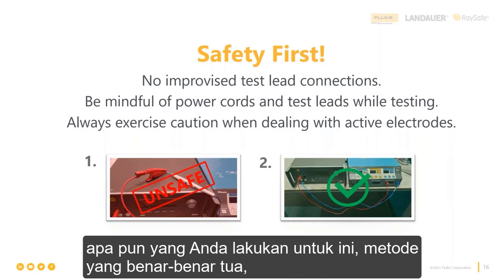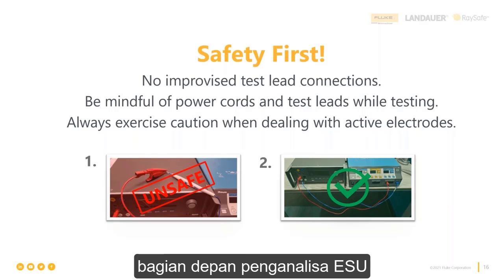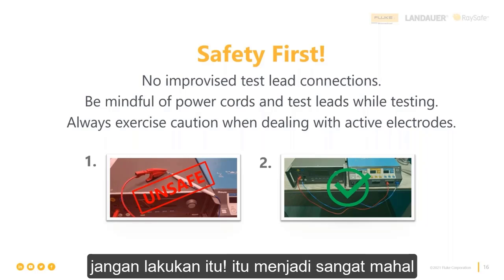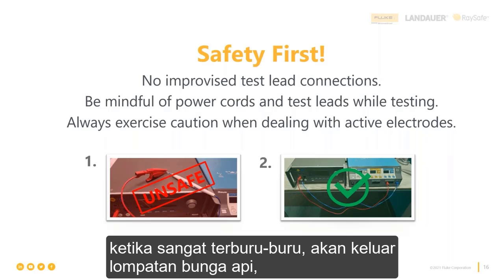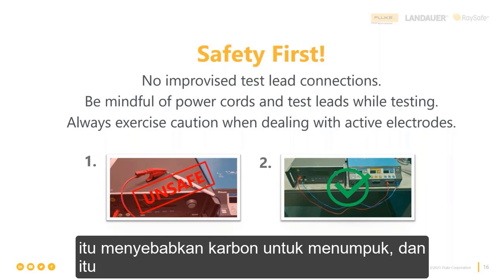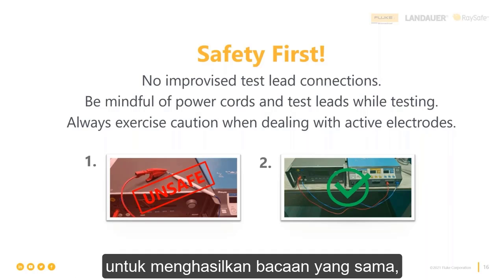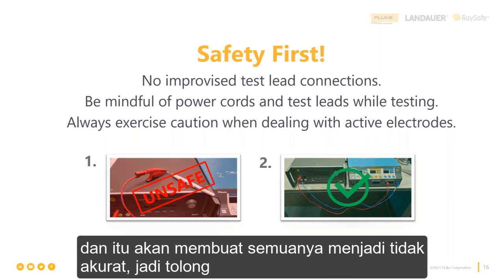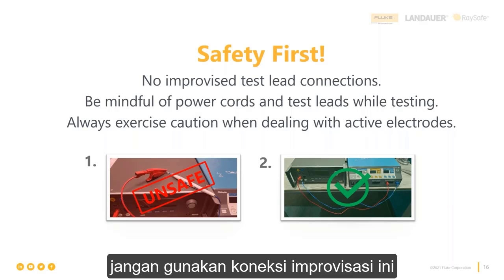And please, whatever you do, for us really old school guys who used to stick the pencil in the front of the ESU analyzer, don't do that. It gets really expensive in a big hurry. It'll arc it out. It causes carbon buildup, and it's going to start taking more energy to pull the same readings. And it's going to throw everything off. So please don't use these improvised connections.